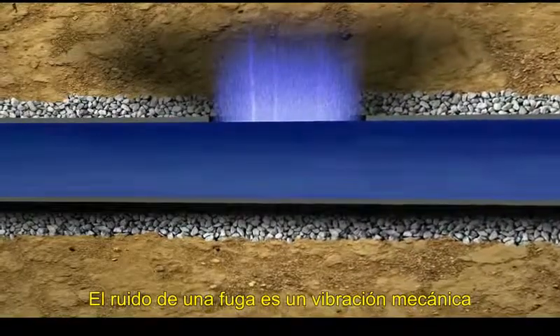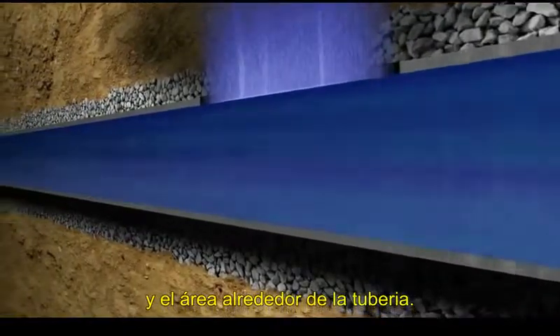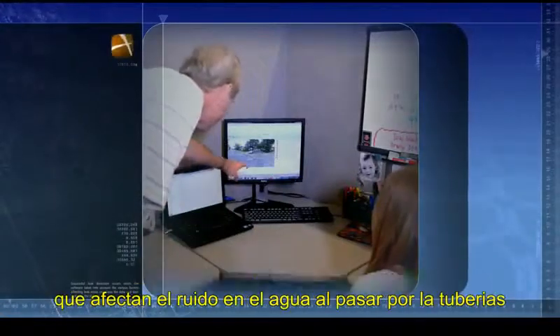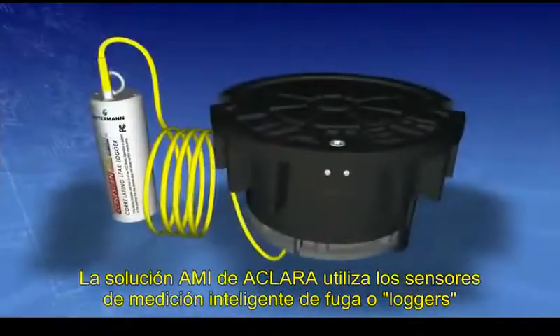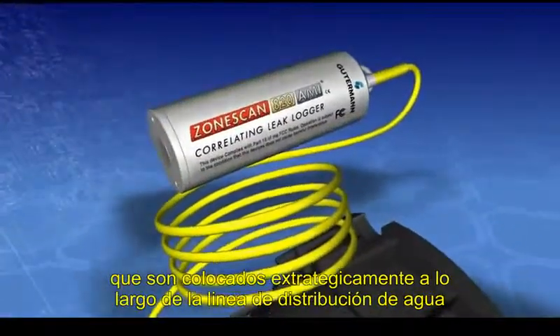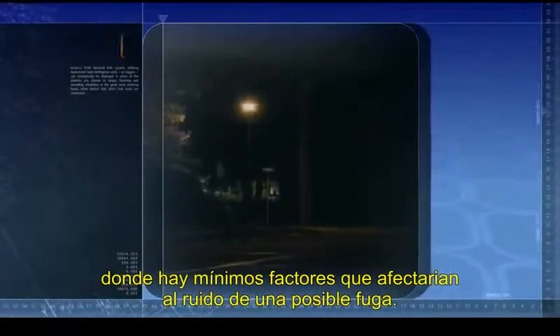Leak noise is mechanical vibration that occurs when a rupture or break in a water main produces a pressure differential between the water in the pipe and the area outside it. Successful leak detection occurs when the software takes into account the various factors affecting leak noise, correlates the data, and then pinpoints the leaks. An ACLARA STAR Network AMI system, utilizing Gutermann leak intelligence units, or loggers, can strategically be deployed in areas of the pipeline you choose to target, listening and recording vibrations in the quiet early morning hours when factors that affect leak noise are minimized.